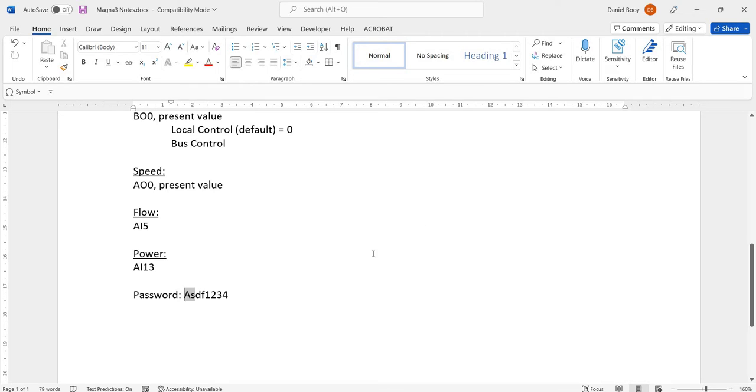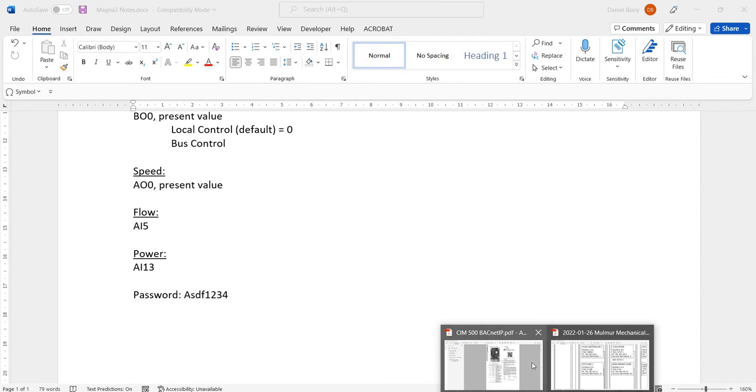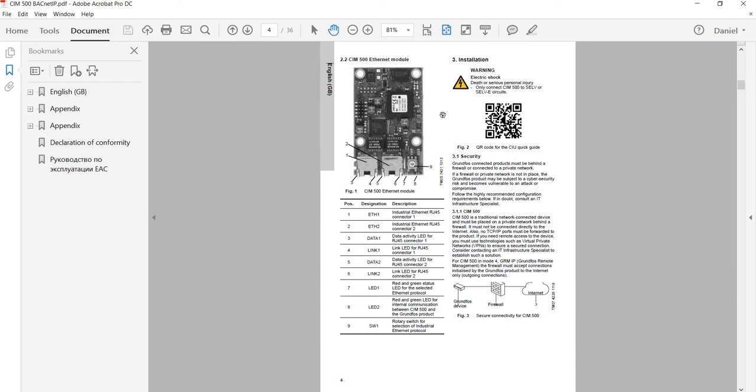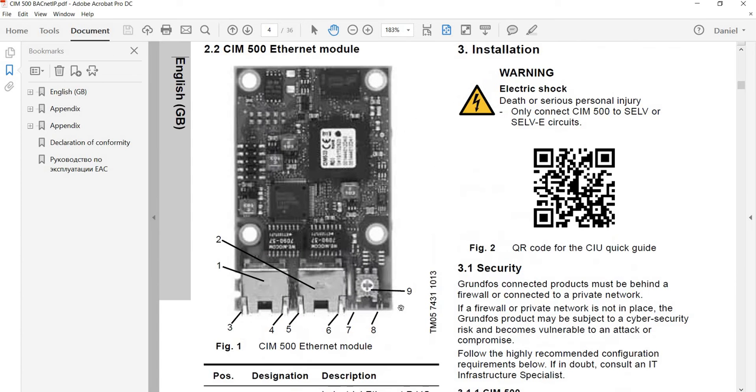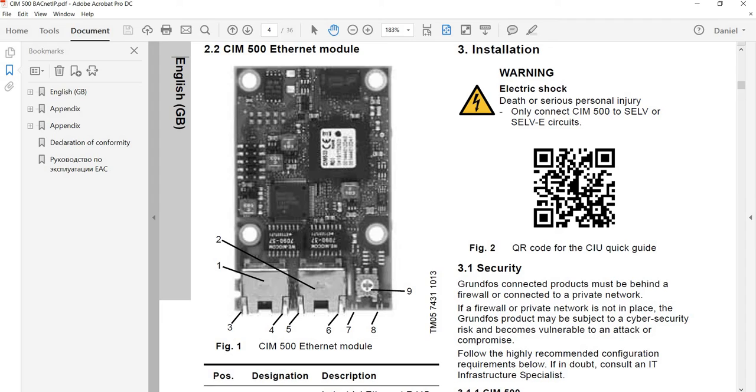This is a password for our login to the controller. And now the first thing we've got to do is go to the CIM500 card and there's a rotary dial in the bottom right here. Turn it clockwise two ticks to the two. It'll be like 45 degrees down to the right pointing at it and it's hard to see. It's two clicks to the right from the default. And then its default IP address is 192.168.1.100.